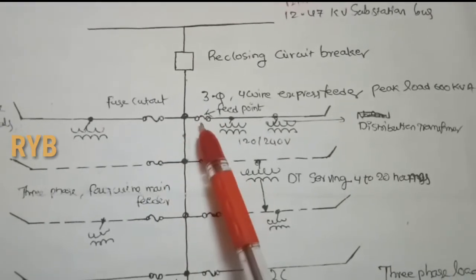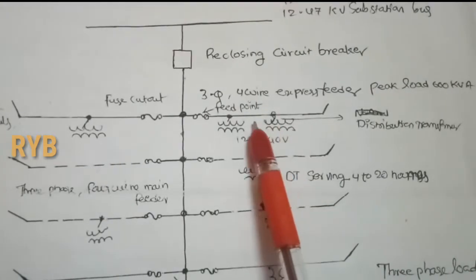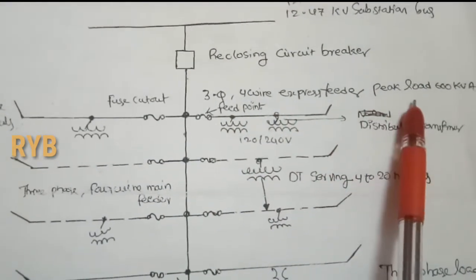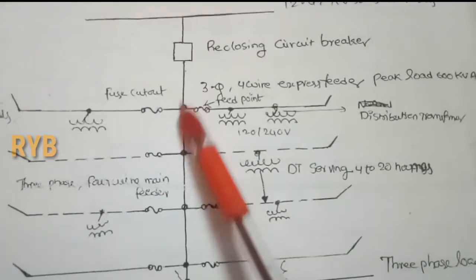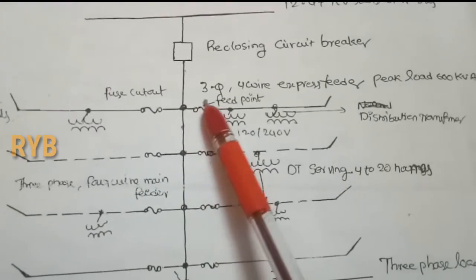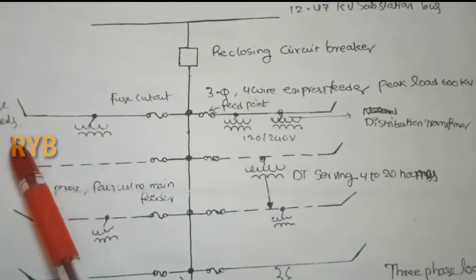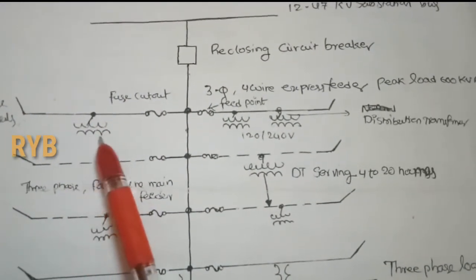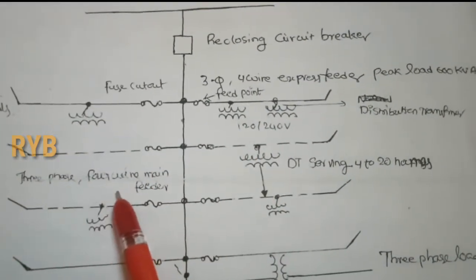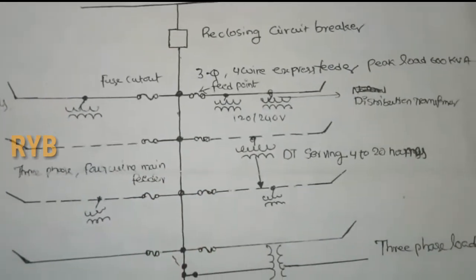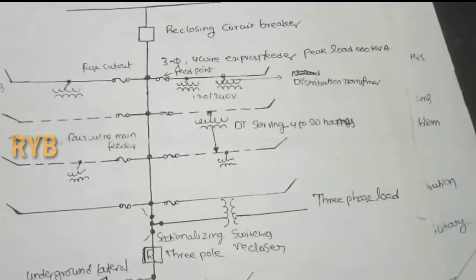Fuse cutouts are provided for branches. Distribution transformer locations are shown along the feeder. A three-phase four-wire express feeder with a peak load of 600 kVA comes directly to the load center without any tapping — this is called an express feeder. Two-phase and single-phase laterals are also shown, along with distribution transformer locations, completing the diagram representation of the primary distribution feeder.